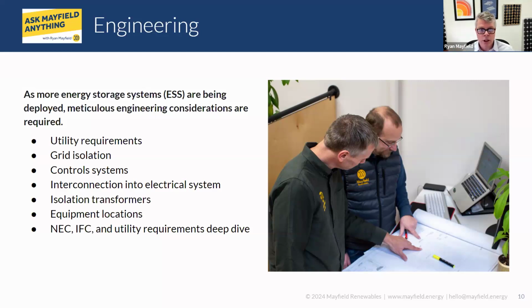We can do a manual connection from utility over to the backup system. As we described, that's something we're doing in some of our systems because of the way load shedding - exactly what 702 is addressing - is happening. Some of the loads that are on these panels getting backed up are too much for what the energy storage system can do. So if we provide a manual method, they can manually turn everything off or choose which loads to turn on and then switch over. That's one way to meet it.